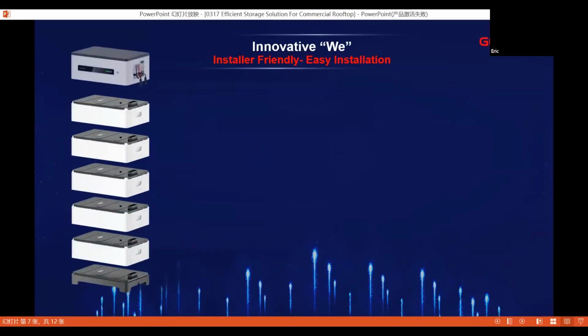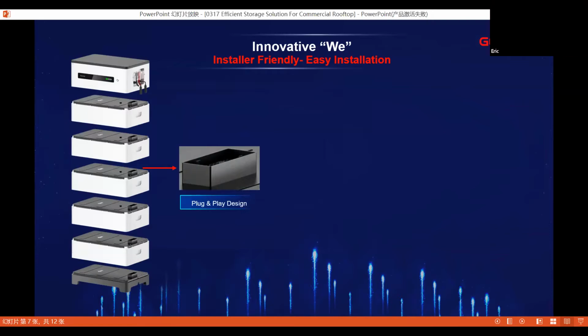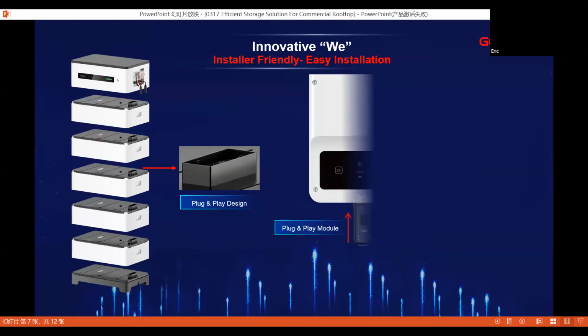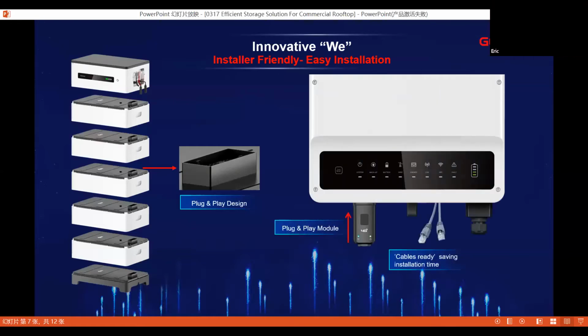And the Lynx F battery is very easy to install. We use the plug and play design. You just need to plug each module together, then the installation is finished. You just need to connect the power cable and the communication cable to our inverter. So I think if you are using this Lynx F battery, the installation time may be less than 20 minutes. Very easy to install. It's just like the Wi-Fi module. The Wi-Fi module just needs to be plugged in, plug and play.